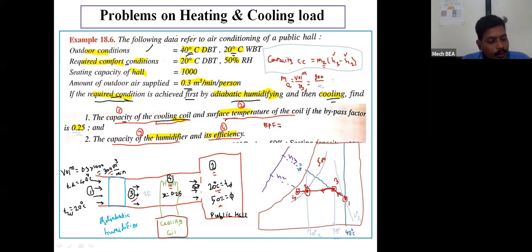The bypass factor formula cannot simply be memorized. In each situation you have to derive the bypass factor formula based on the problem's setup. Just remember the basic concept: bypass factor is nothing but the ratio of temperature difference between coil and outlet, divided by temperature difference between coil and inlet. Who will tell me what the bypass factor formula will be in this case?